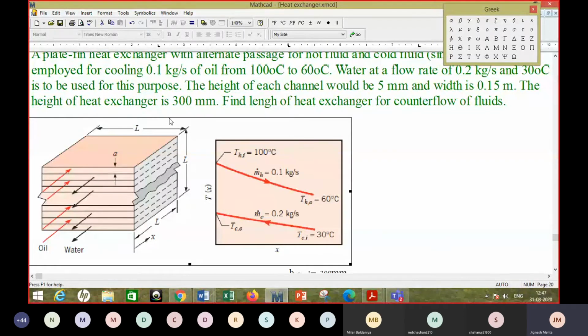So you're pumping it from the opposite direction. You are making a counter flow heat exchanger. Many times these heat exchangers are cross flow also, but in this case it is shown as counter flow, which from the thermal point of view is the best configuration. If you are using cross flow, then you have to get the right chart and formula for finding the correction factor for the log mean temperature difference.